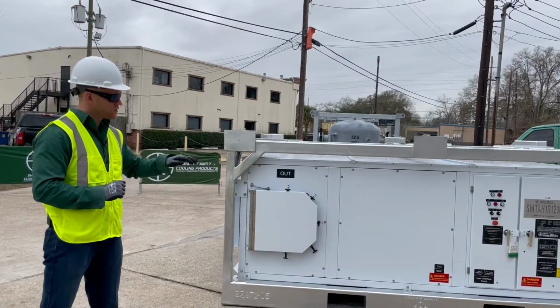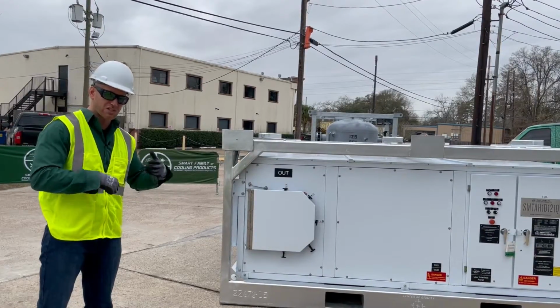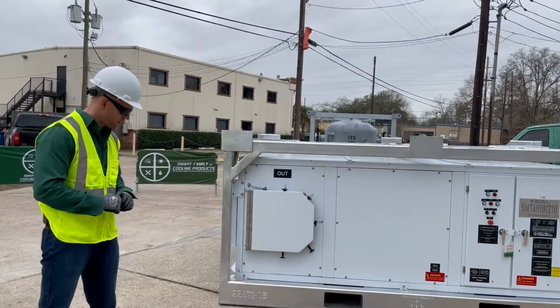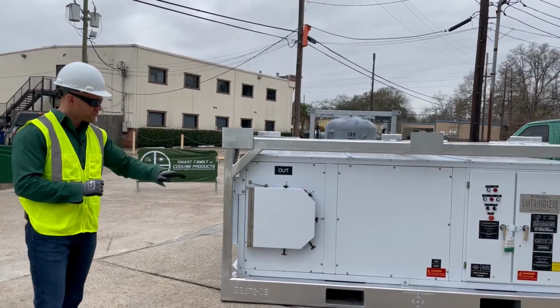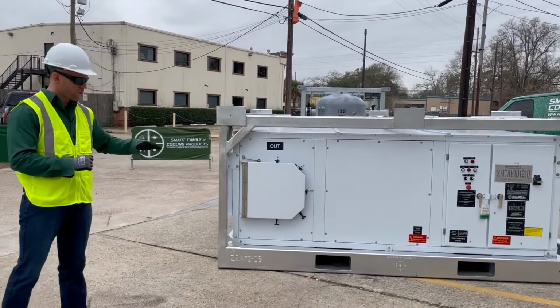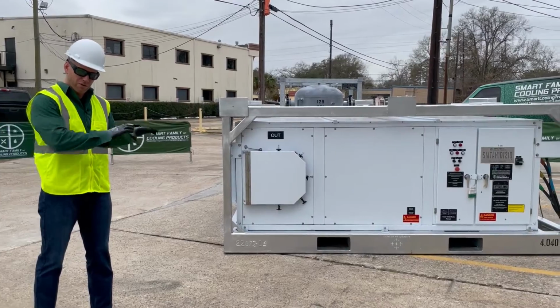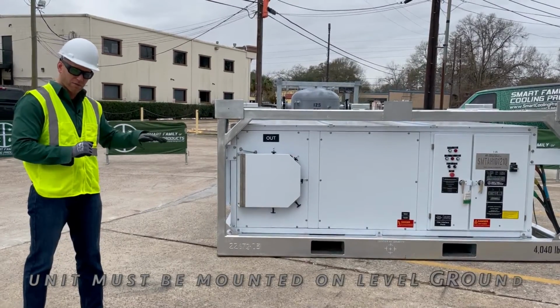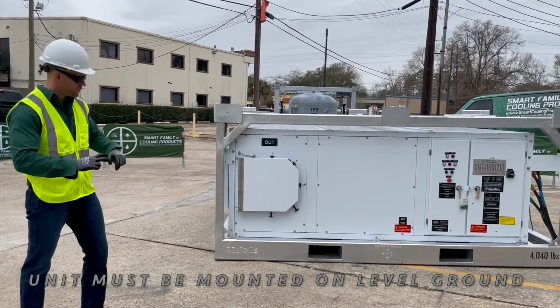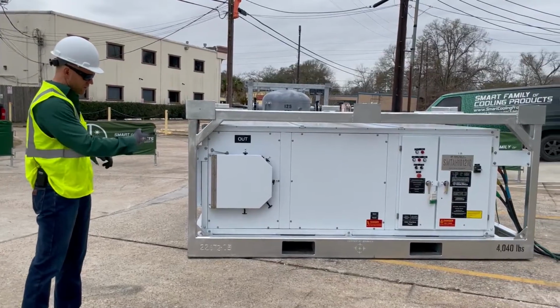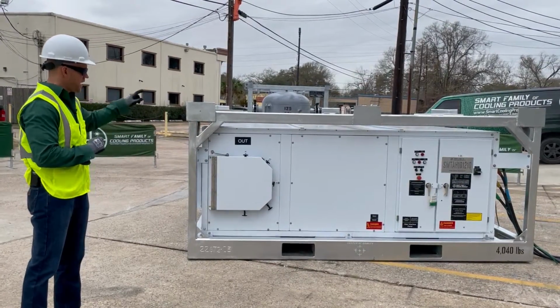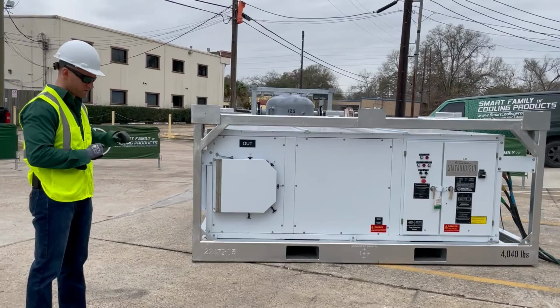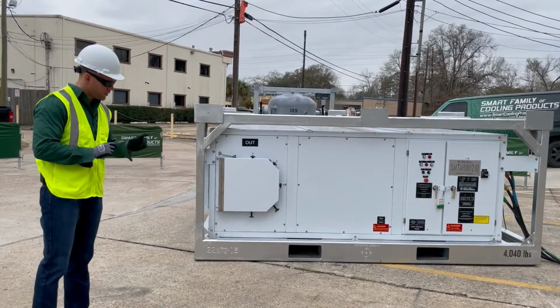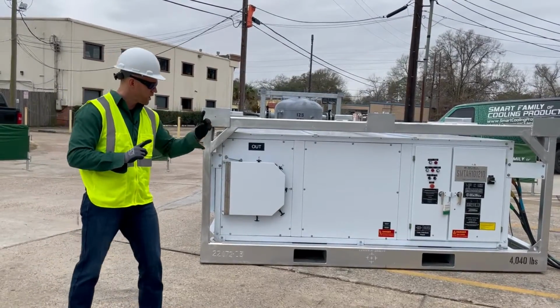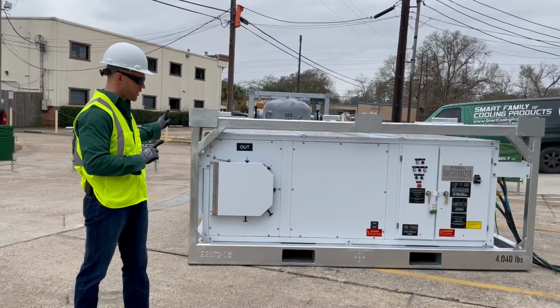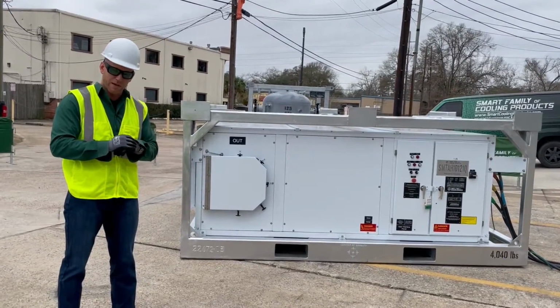We also want to look for damage to make sure that the unit won't damage itself when it goes and it runs, okay? On the job site, as we're doing our inspection, we also want to make sure that the unit is mounted or set on level ground. And please note that these units typically have fork pockets with marked center of gravity and then overhead lifting points, okay? All right, so when we receive the unit, step number one, we walk all the way around the package and we inspect the unit for damage.